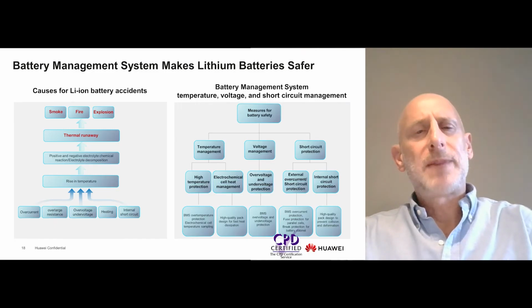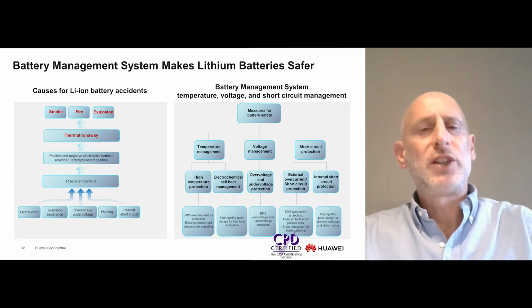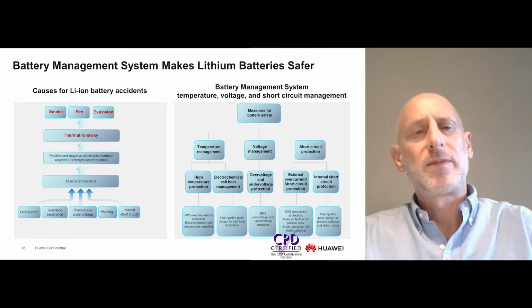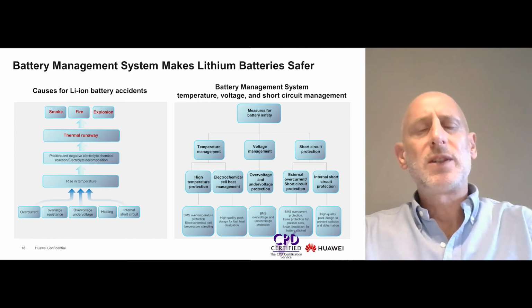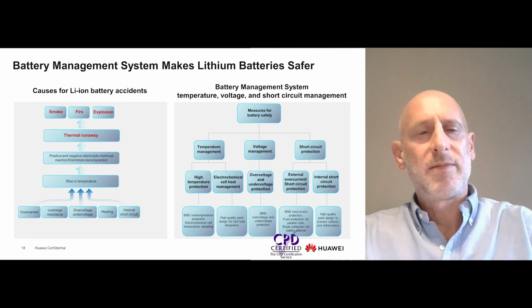A typical lithium battery failure occurs when the cell fails. The internal resistance of the cell increases, internal damage causes a short circuit, and overcurrent may cause the cell temperature to rise. At high temperatures, the positive and negative materials of the battery decompose, resulting in thermal runaway causing smoke and fire.